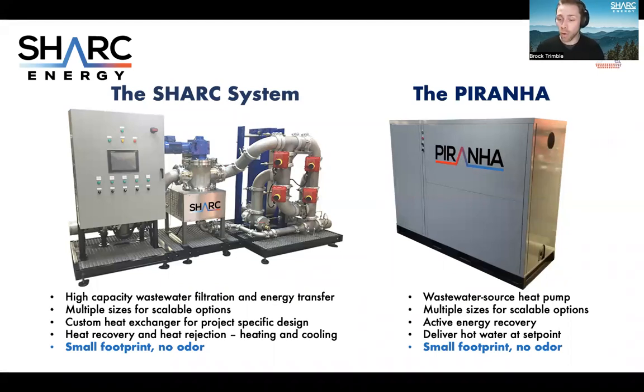On the smaller side, we have the Piranha piece of equipment, which itself is a very specialized and dedicated wastewater source heat pump. With this unit, we're actively recovering energy and taking basically every BTU that's available in that wastewater stream down to a certain low limit, and using this energy to transfer into a domestic hot water stream, providing hot water at a set point directly into your building space. Both of these options have multiple sizes for scalability, from anywhere around 100 gallons a minute up to about 2,500 gallons a minute of wastewater flow and filtration with the SHARC unit, and then multiple heat output capacities with the Piranha. Everything is very scalable for your systems.